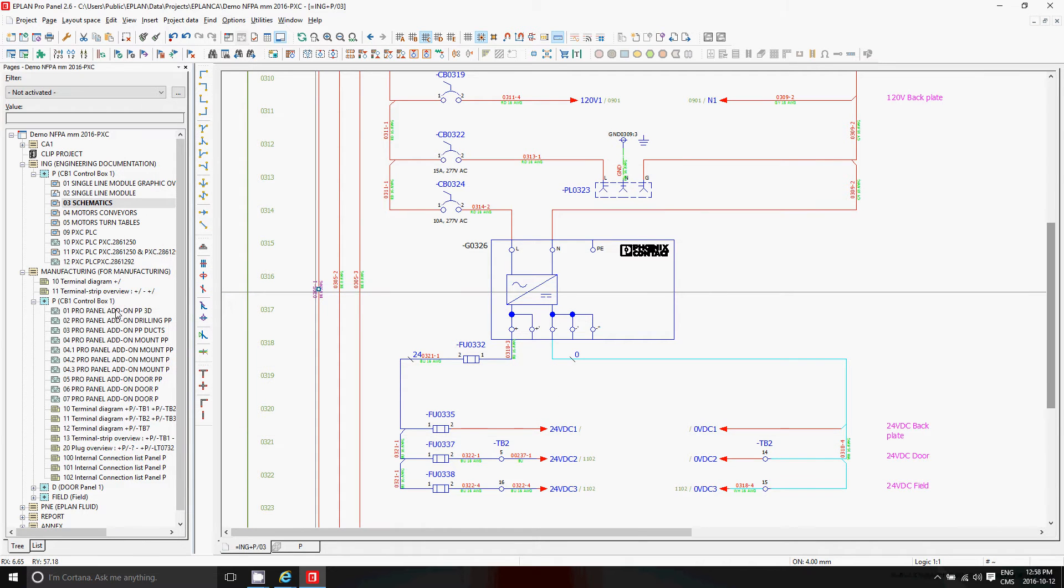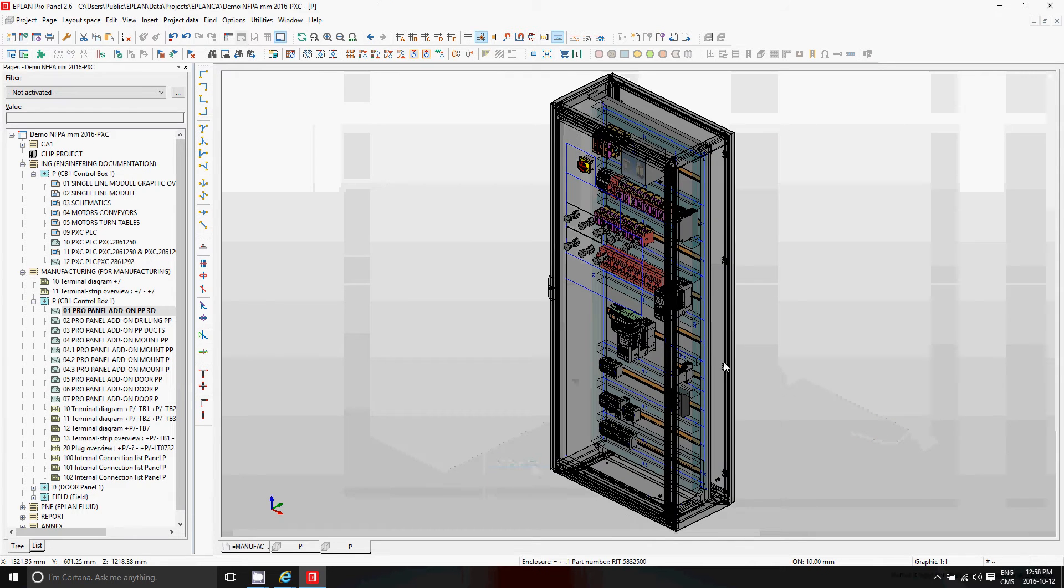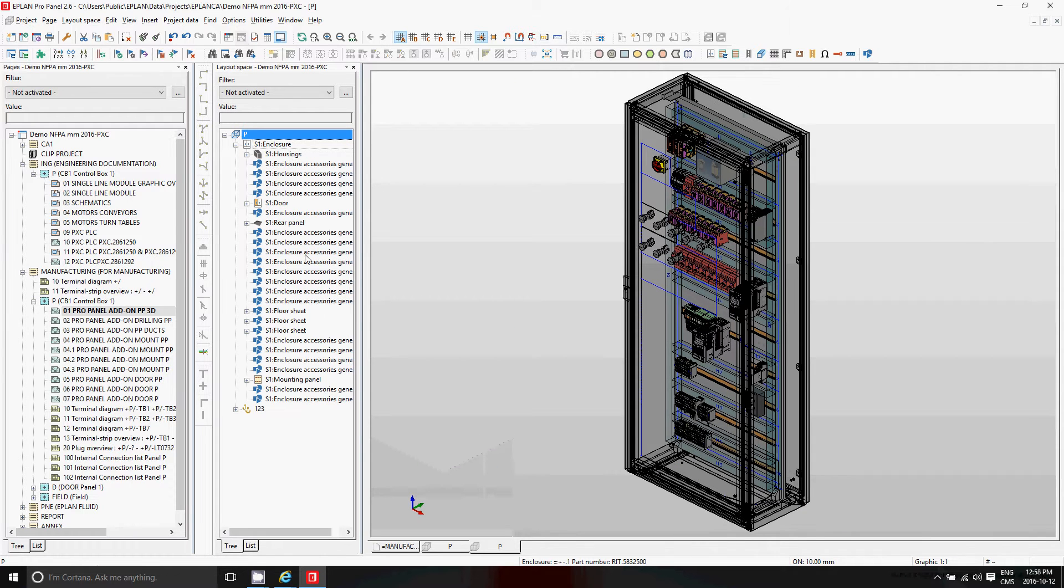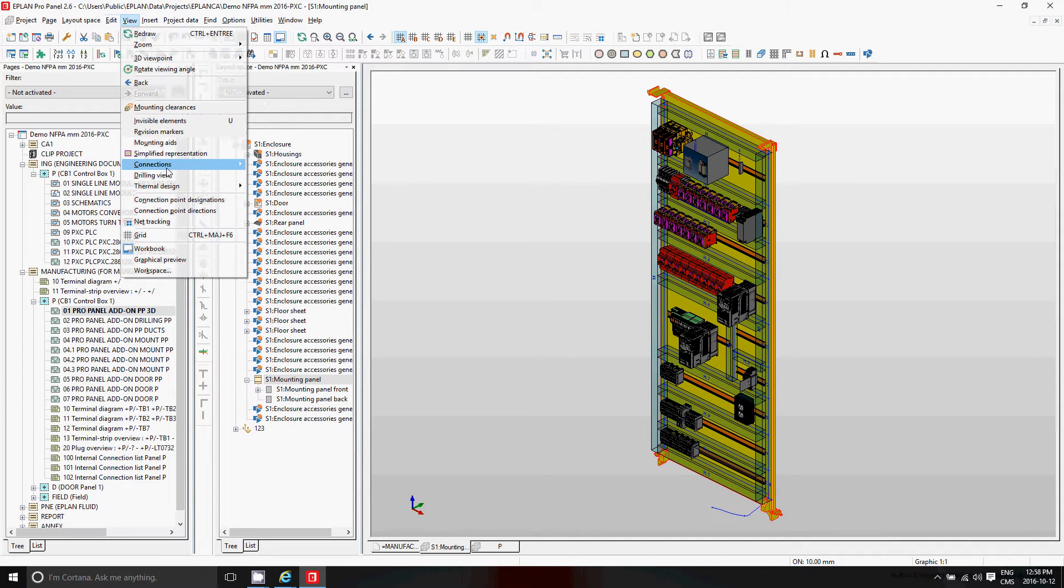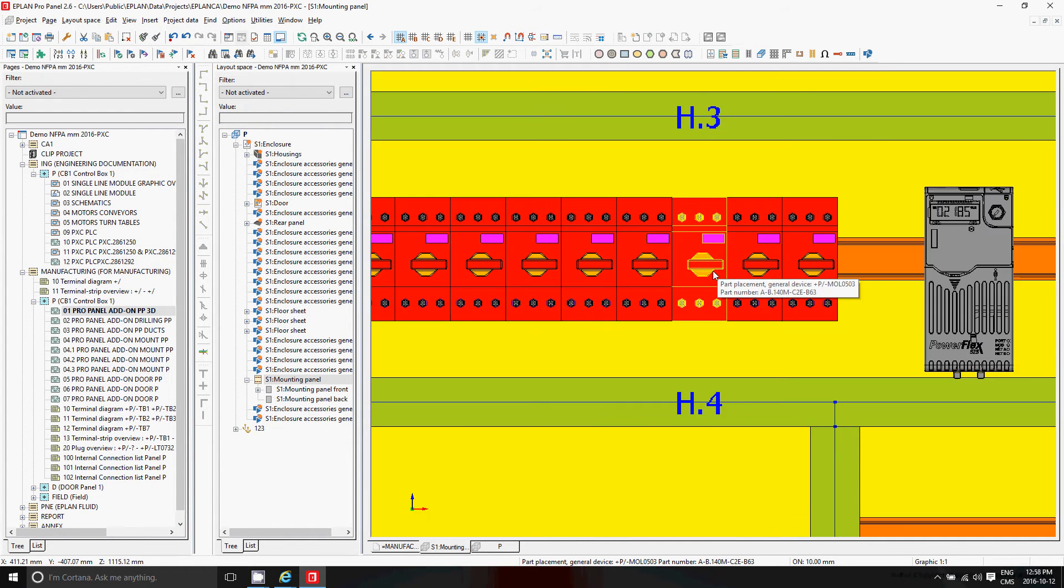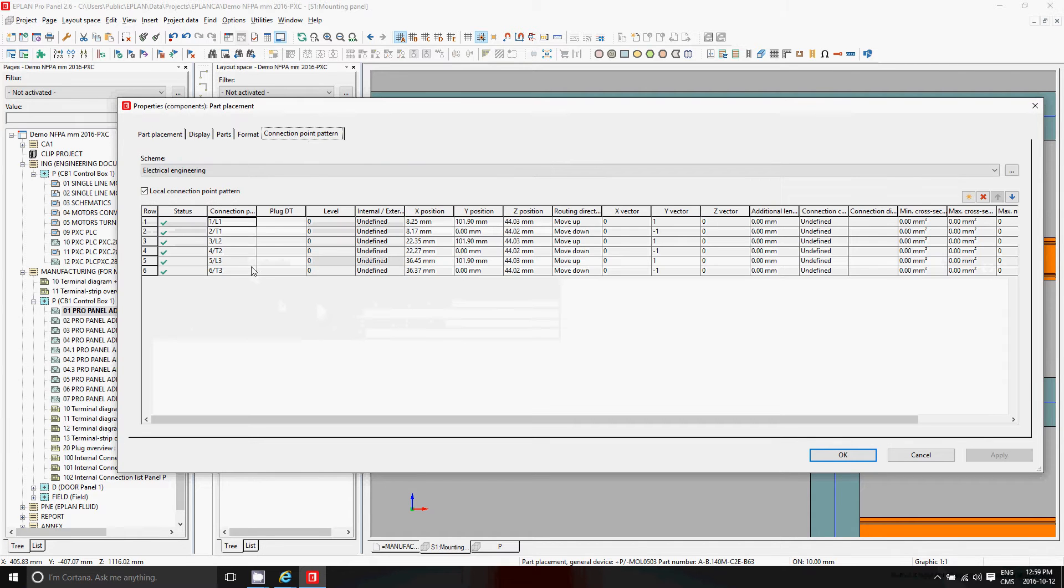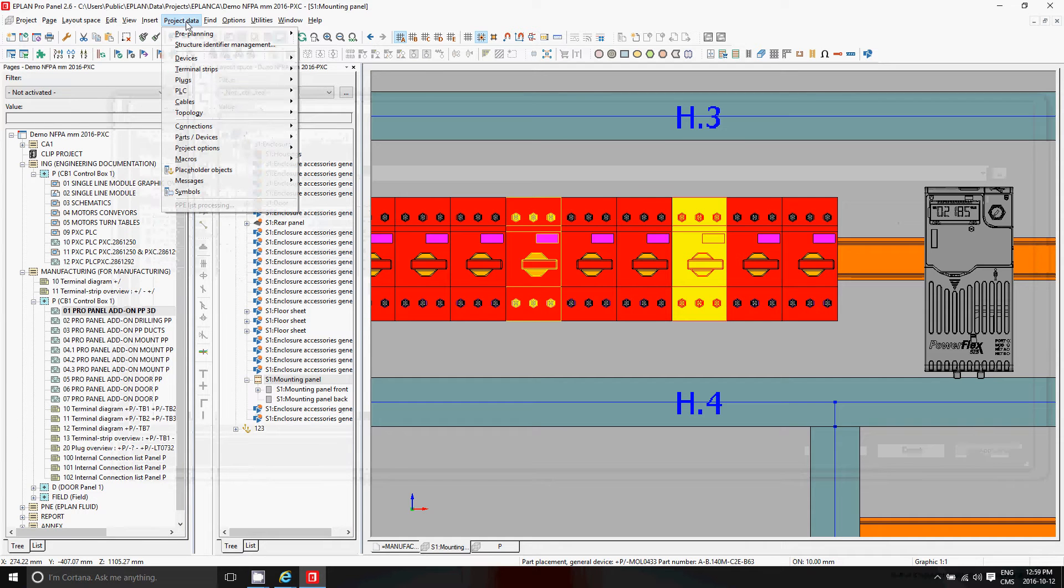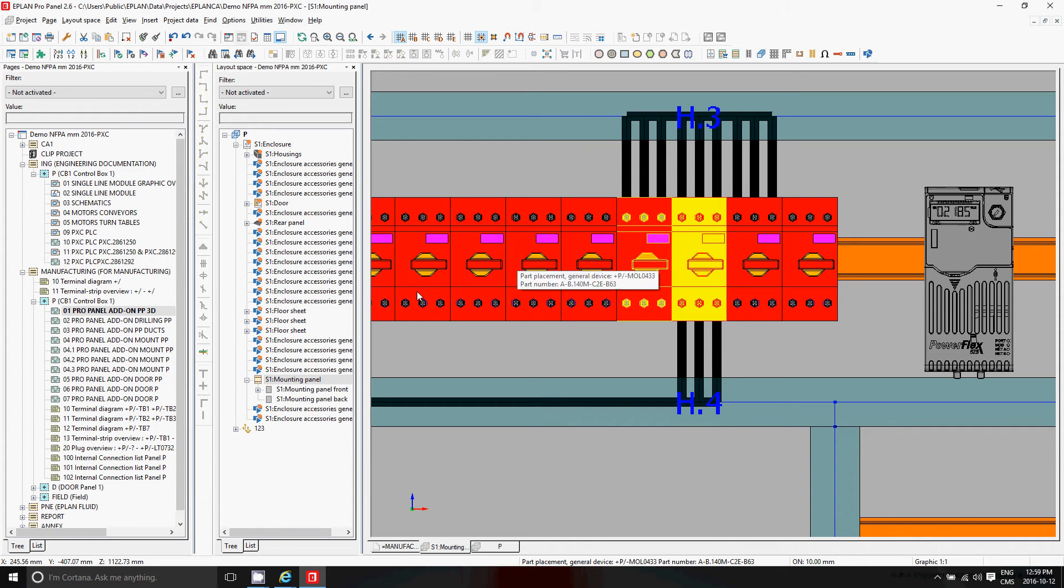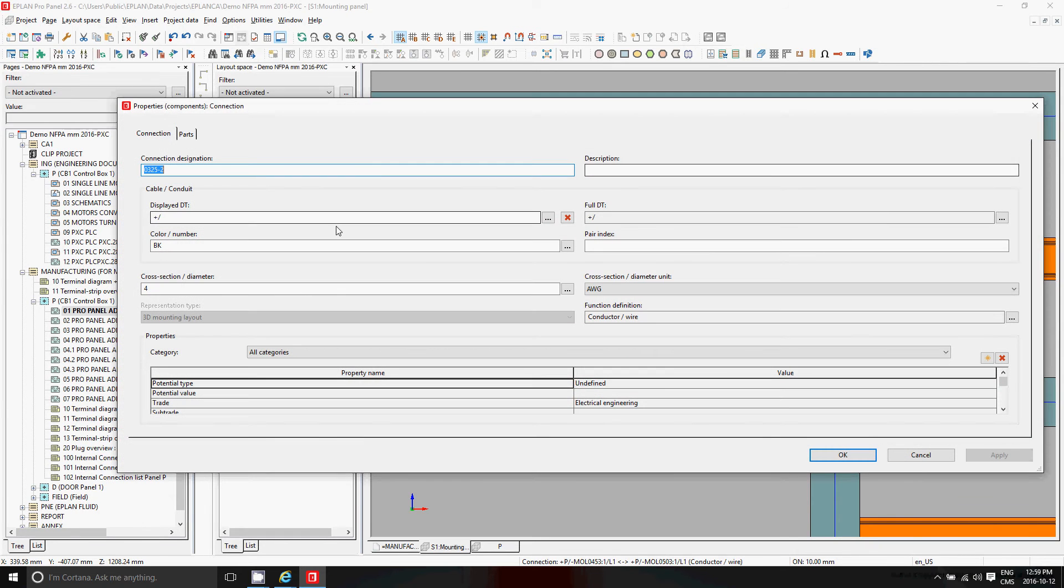Parallel to this, we have the panel layout. The panel layout in ProPanel is done in 3D. We work with here individual surfaces, like the mounting panel, and inside this mounting panel, we place our devices. Now, these devices, let's take a look at the front view here. Every device has a device tag that is related back to the original schematics, and has some connection points associated with it. And through these connection points and the wire information that we have provided in the schematics, we can do some sort of routing. This primarily gives me the wires, and each of these wires has now a specific length associated to it, driven directly here from the 3D.